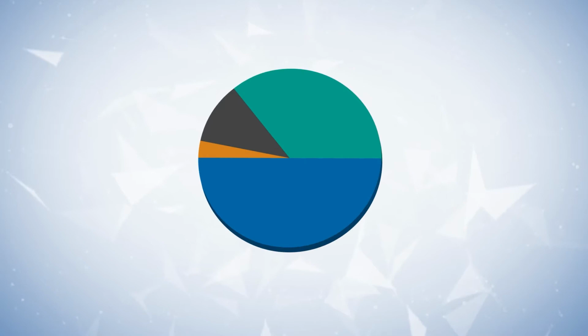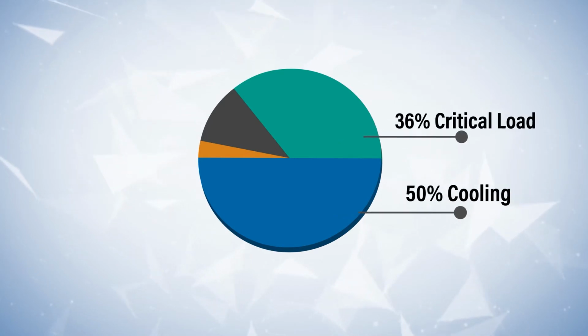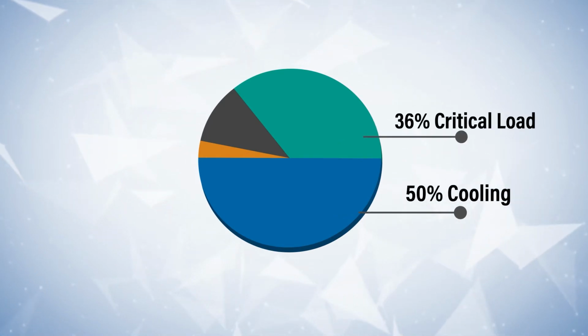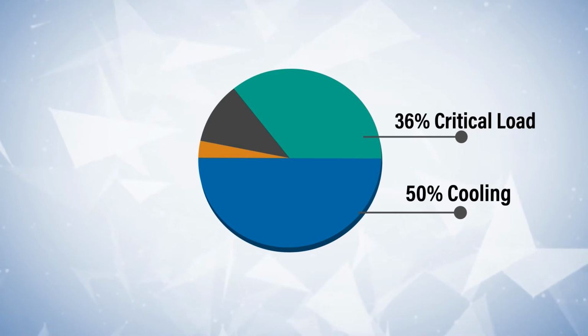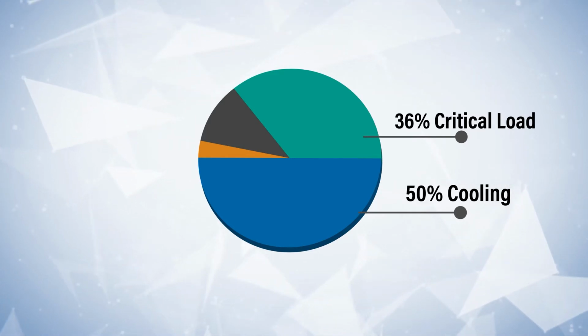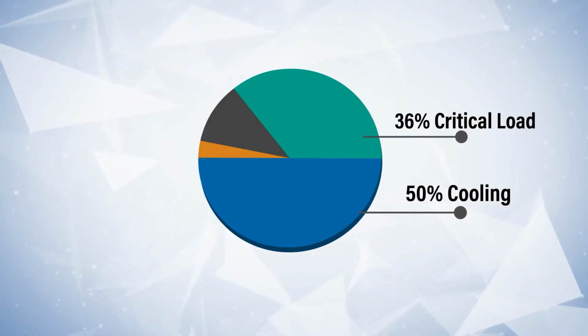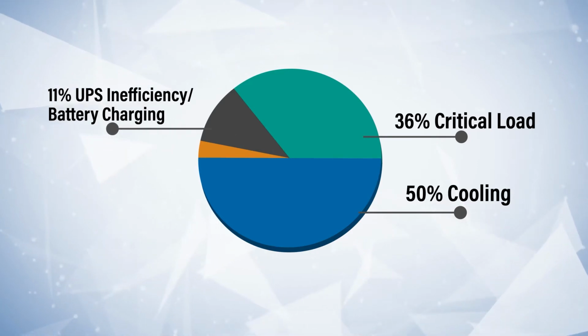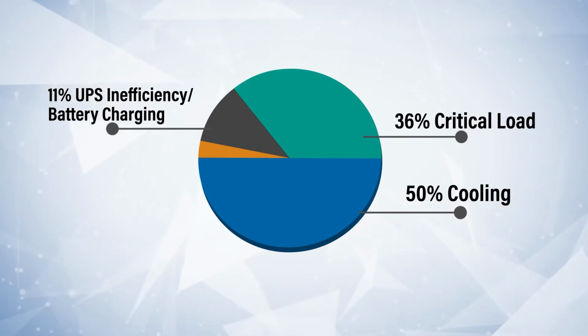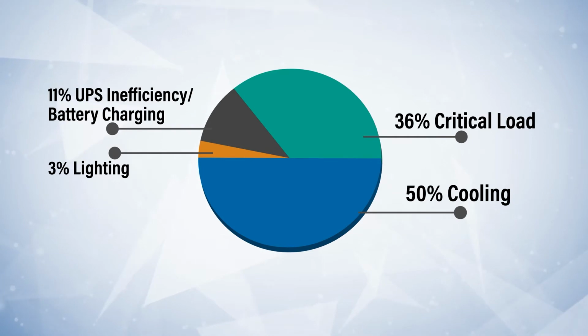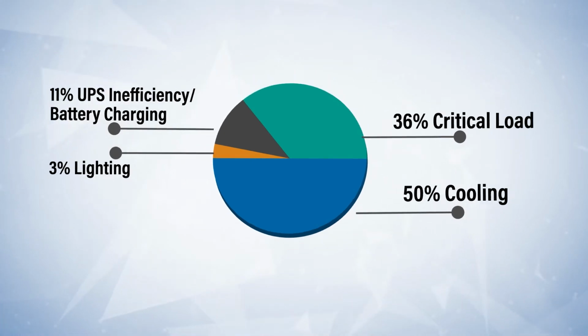To accurately calculate the power, first you need to know where the power is going in the data center. The majority of the power is used in cooling, that is 50%, and the next is critical load. It takes 36%. We will explain what critical load is in a later part of this video. Then 11% goes to the UPS, inefficiency and battery charging, and 3% is lighting load, which many data center designers ignore, but we would take into consideration.